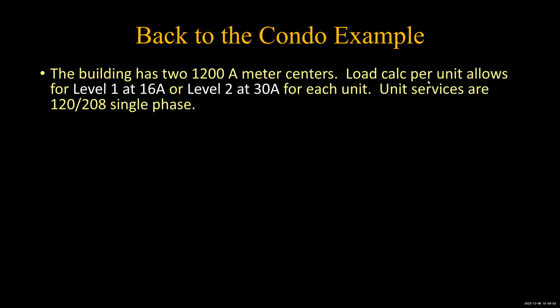So let's see, talking about loads for EV chargers and condo services. Are you talking about individual, connected directly to each condo load center? 220 for overall building service load. Yeah, see, that's 63 condos with the 23%. When you do the individual condo loads and then take the 23%, it's probably going to come pretty close. This would probably have something in a really big service. 63 would have probably almost 3,000 amps of service.